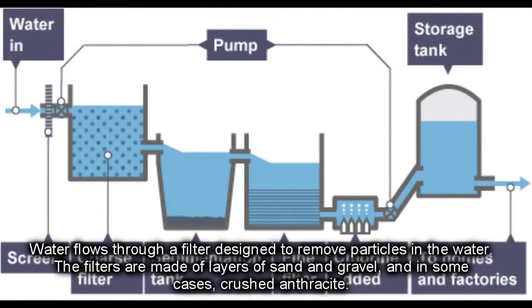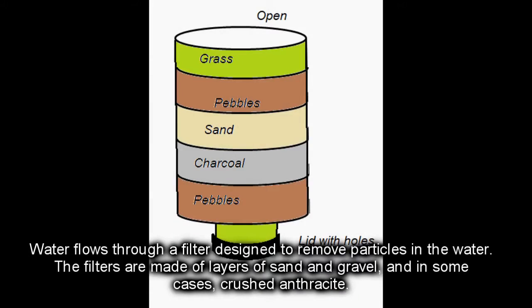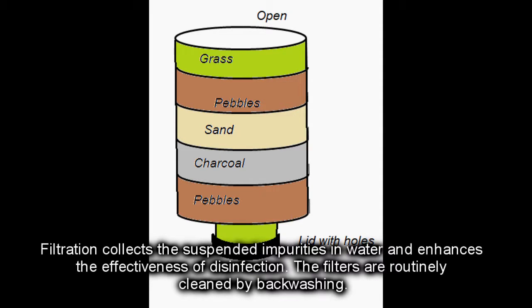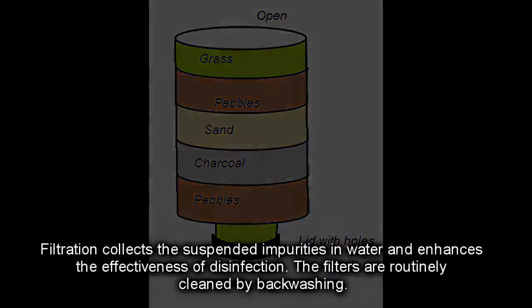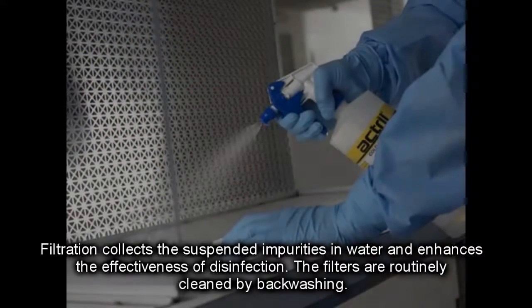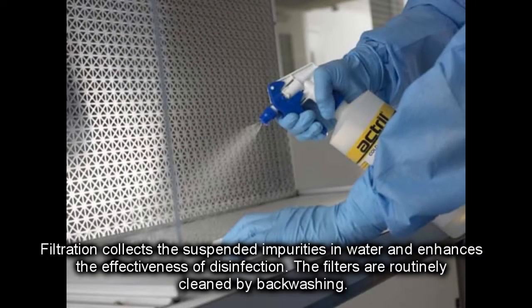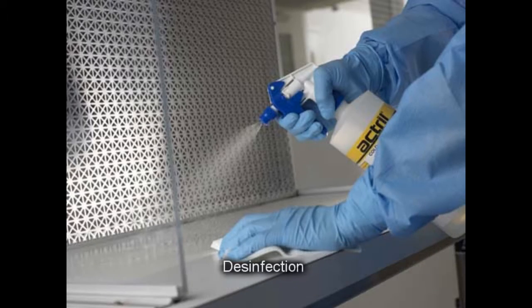Filtration. Water flows through a filter designed to remove particles in the water. The filters are made of layers of sand and gravel, and in some cases crushed anthracite. Filtration collects the suspended impurities in water and enhances the effectiveness of disinfection. The filters are routinely cleaned by backwashing.